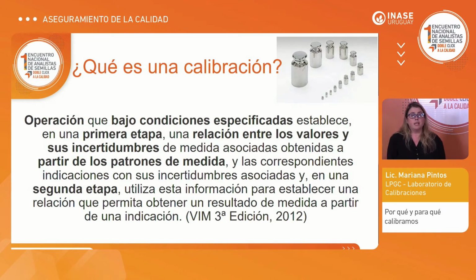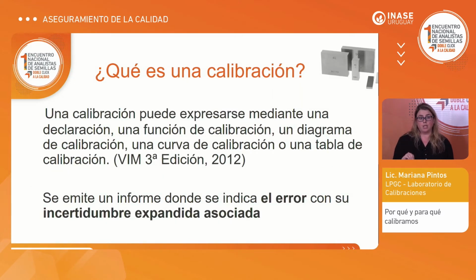So let's see the definition of calibration. For all the definitions we are using for this presentation, we will be based on the metrology definition. So calibration is an operation that, under specified conditions, in a first step establishes a relation between the quantity values with measurement uncertainties provided by measurement standards and corresponding indications with associated measurement uncertainties, and in a second step, uses this information to establish a relation for obtaining a measurement result from an indication. If we want to understand this definition a little better, what we do is compare the values with the uncertainties associated to the pattern and what the instrument or the tool is showing. So in a second step, we relate this result in order to find an indication.